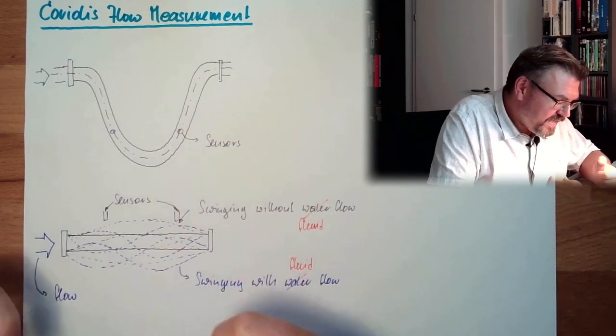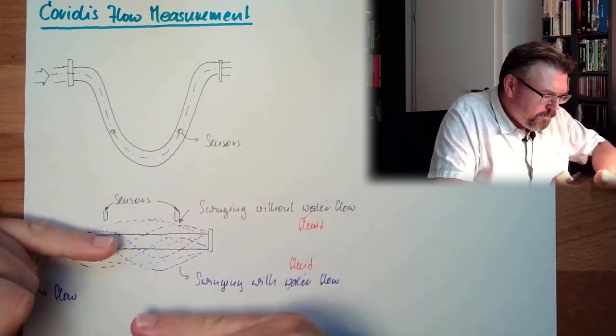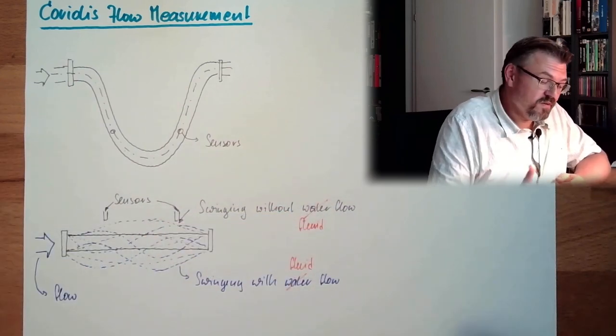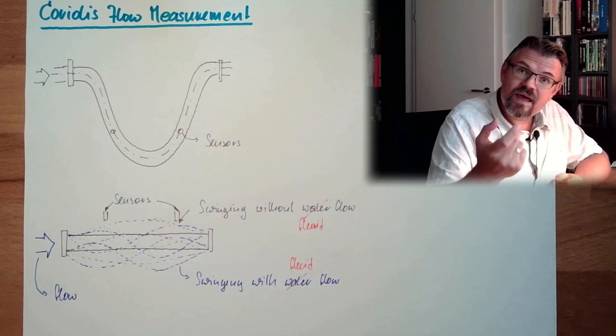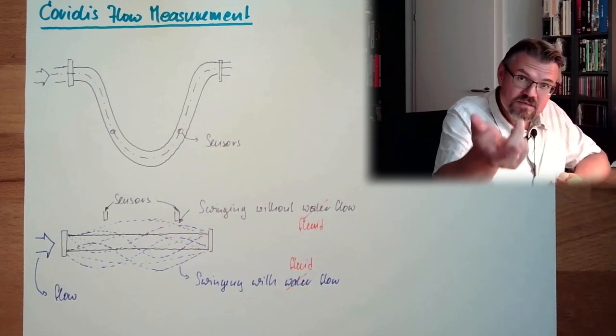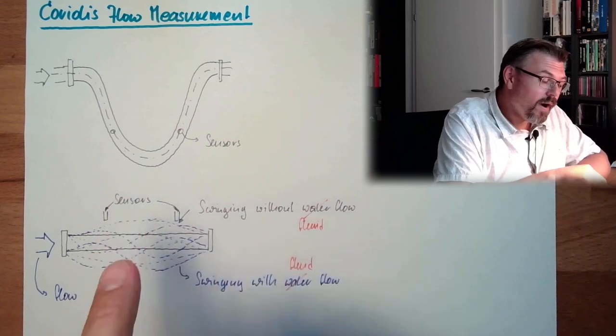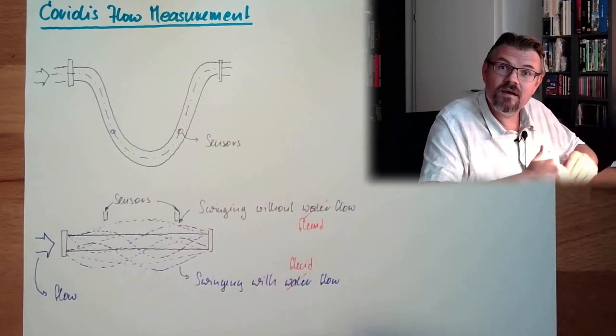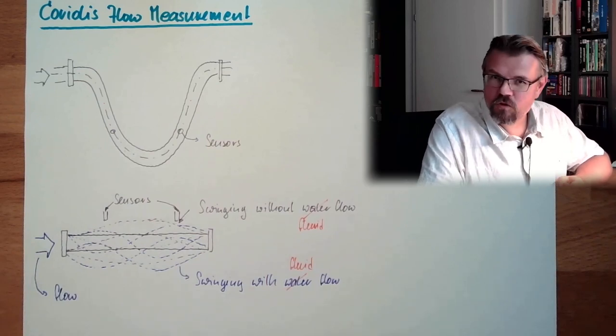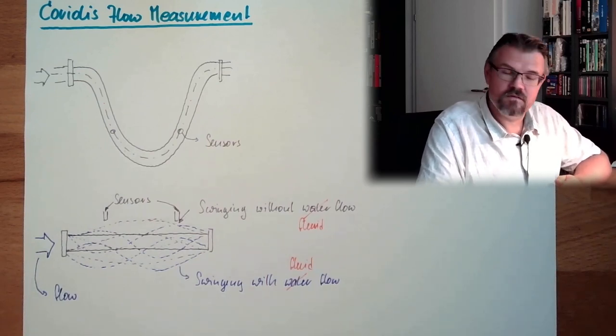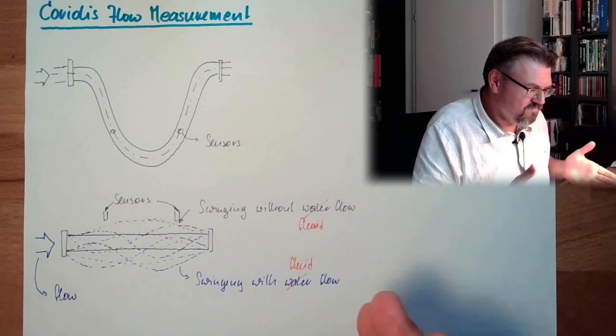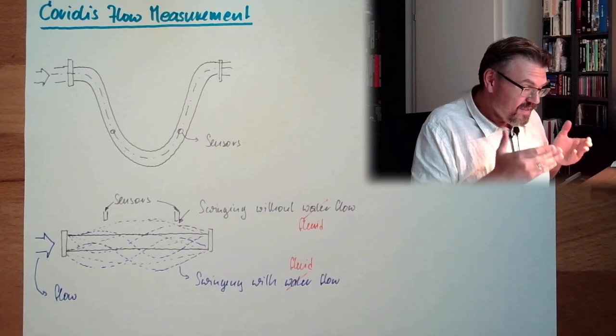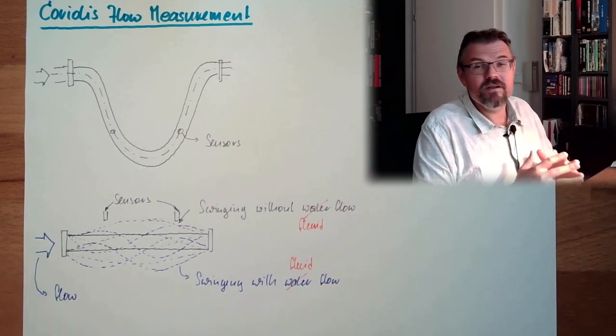And if we now look at the sensors and we are beep, beep, beep, beep, beep, we have a shift in the signals. And this timely shift in the signals is indicating how much disturbance there is in our smooth swinging, and this is indicating how much mass flow there currently is. So, this is the principle of Coriolis flow measurement.